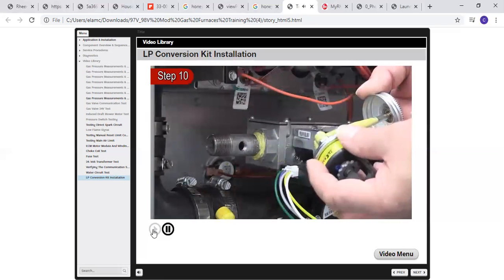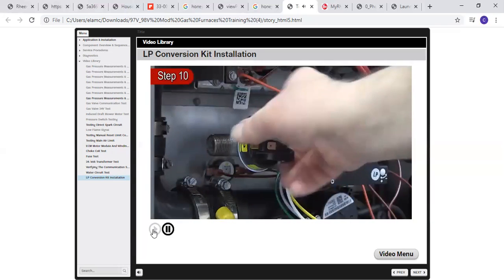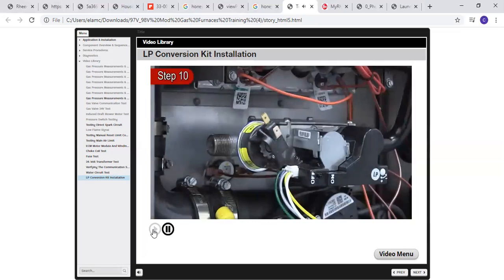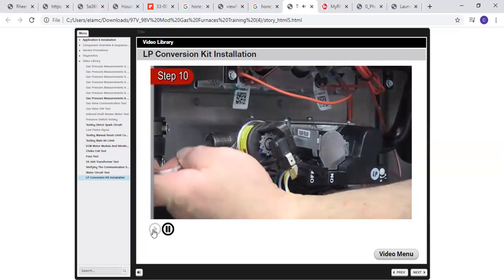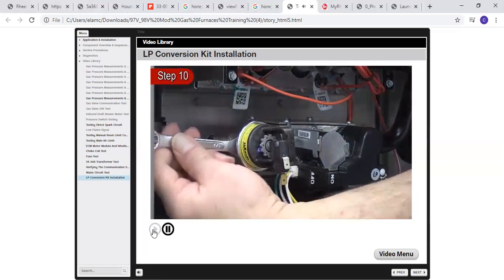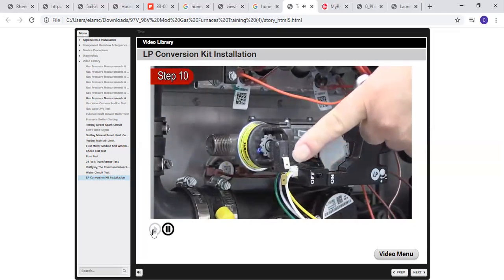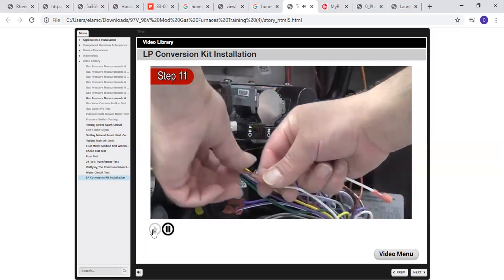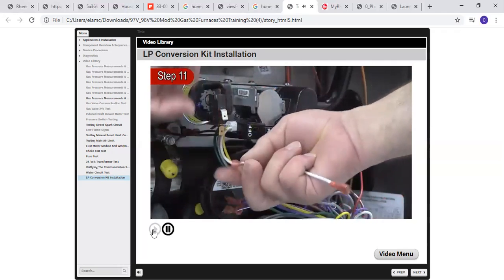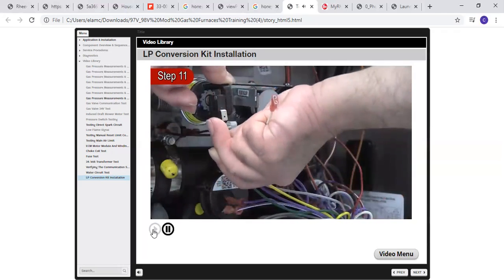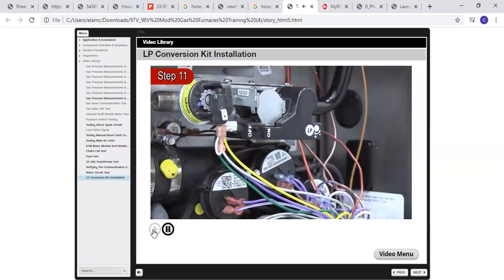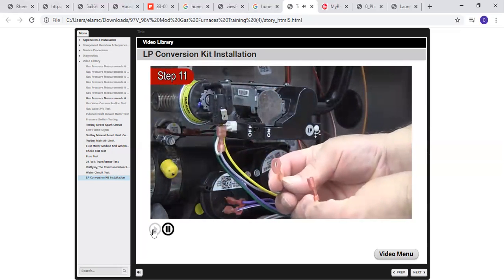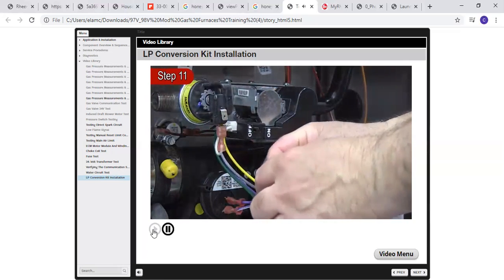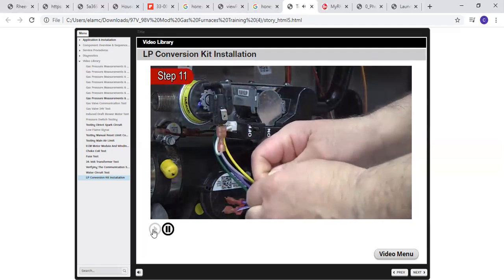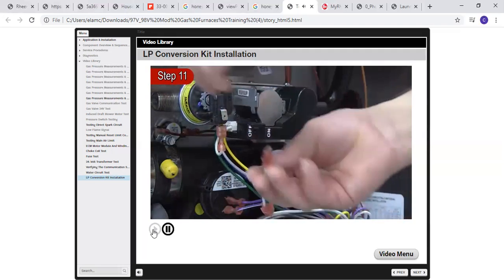Step 10. Install the inlet pressure switch into the tapped hole. Be sure to apply pipe dope or Teflon tape. After tightening, the terminals on the inlet pressure switch should be facing down towards the blower shelf. Step 11. Remove the connection in the white wire going to the gas valve. Plug the 1/4-inch female terminal from the gas valve onto the terminal on the inlet pressure switch. Using the supplied jumper wire, connect the remaining 1/4-inch male terminal on the white wire to the inlet pressure switch.